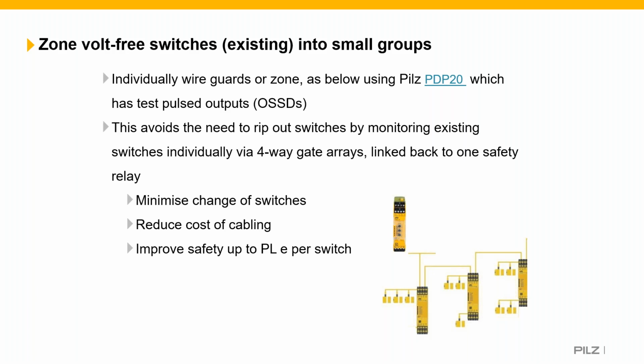So instead of removing existing volt-free switches that you've got on an existing machine, you can add these PDP-20 units to your machine, which will minimize the change of switches, reduce cost of cabling, and improve safety up to PLe per switch, as 99% diagnostic coverage can be claimed.